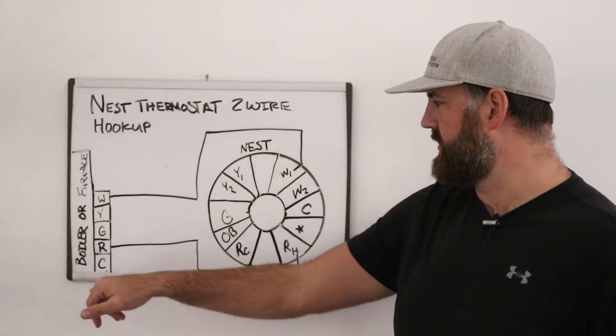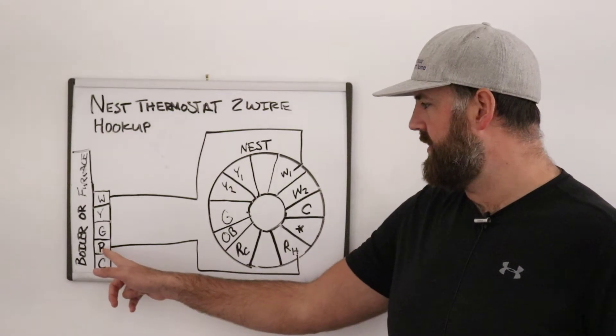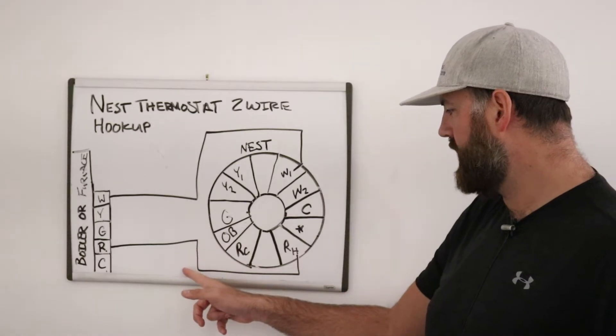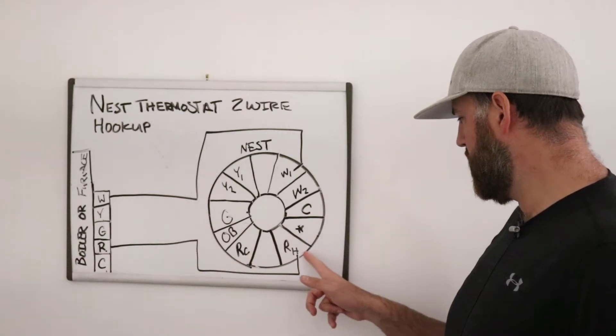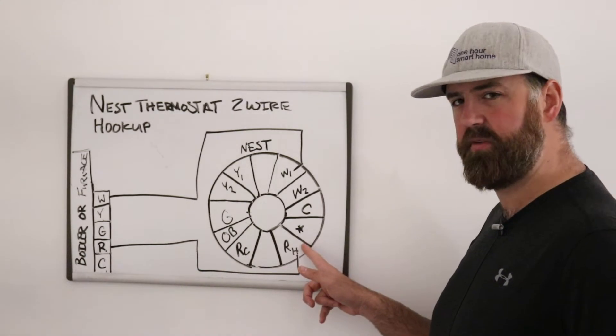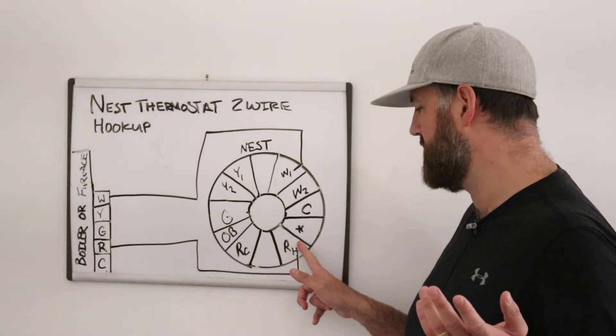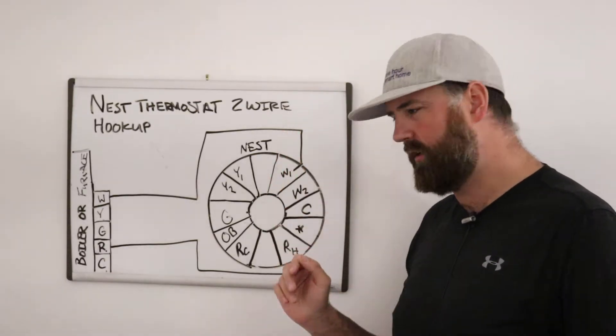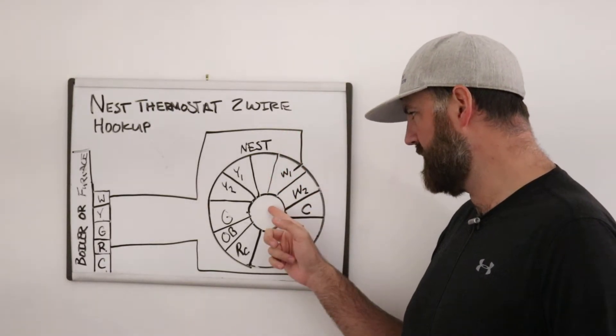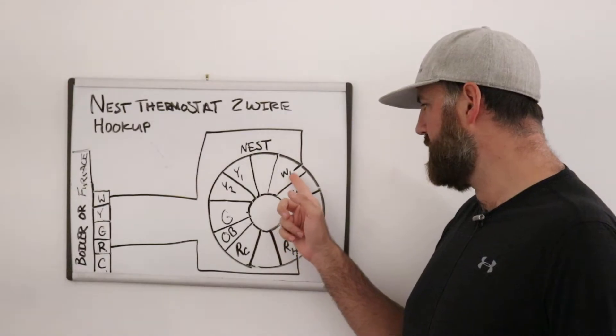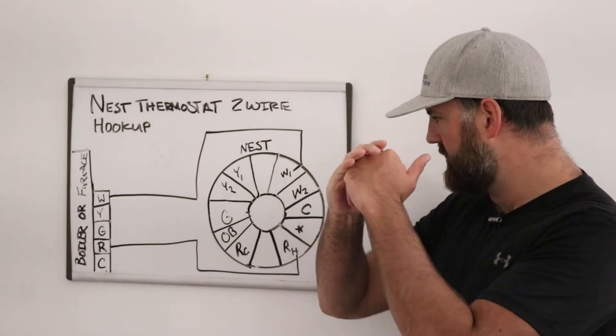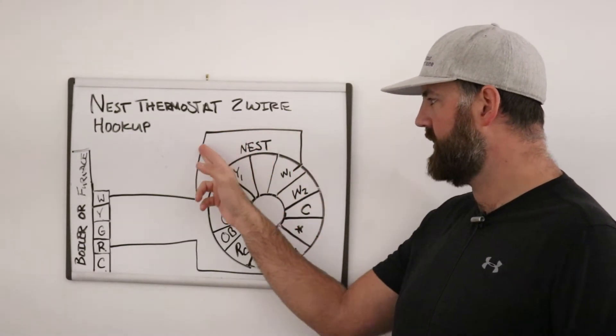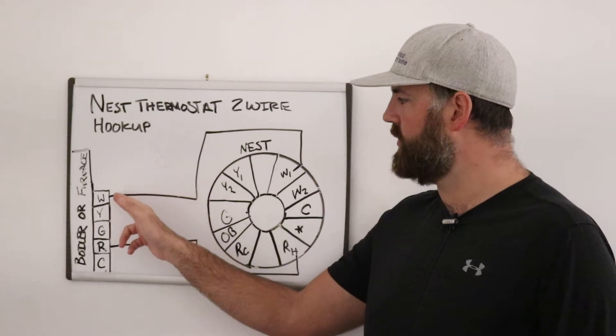And how a boiler or furnace works is that this R terminal is the power terminal and it will go in a wire to your thermostat, whether it was your existing thermostat or your nest thermostat. And then it will go through the nest and the nest is calling for heat. So it's turned up to 90 degrees or whatever temperature it's turned up to. And then that power goes back down through the W1, closes the internal circuitry or switch, power comes back down the W1, goes down the W1 wire, goes to the W1 terminal.